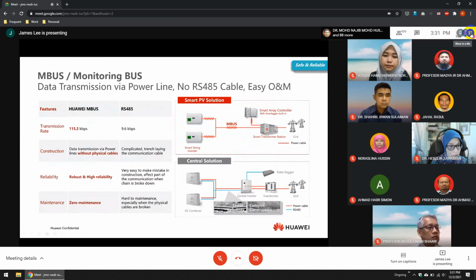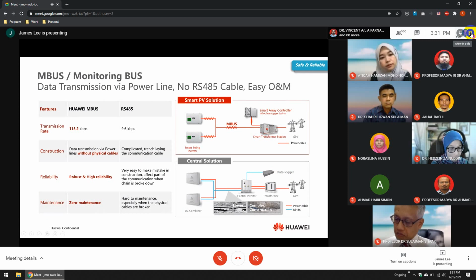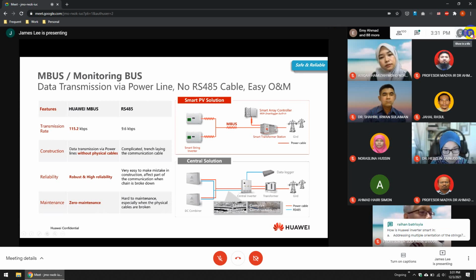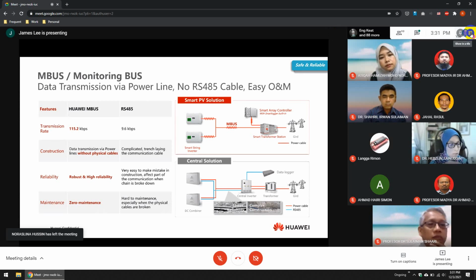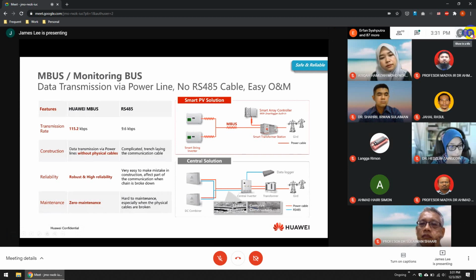Furthermore, we also bring to you this MBUS, which I mentioned earlier. The key advantage is that you don't need additional cabling to enable string level monitoring. It's all carried through the AC cable, which is far more reliable and robust, and buried underground. Whereas RS485 is very prone to failure and unreliable, with lightning strikes being a big problem.